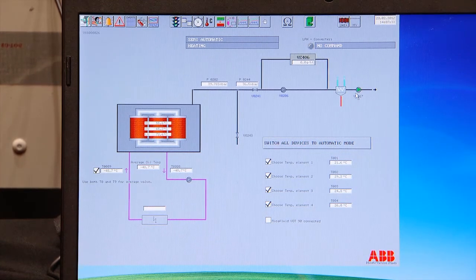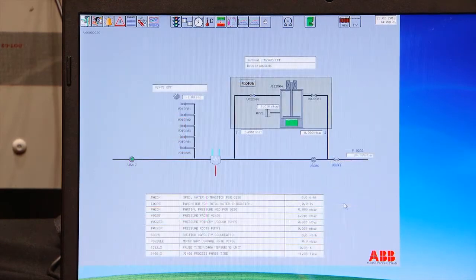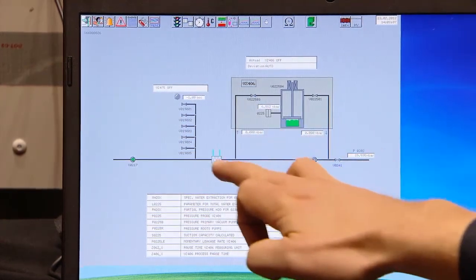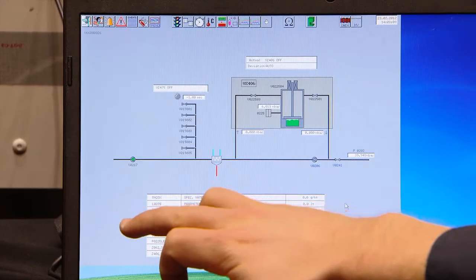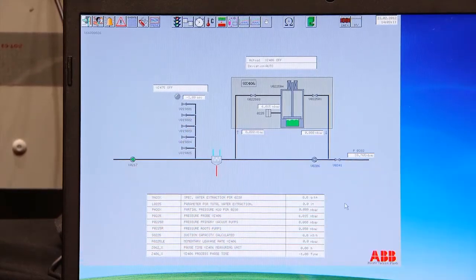Normally the booster is running as well, but now we have a special connection on this setup. The VZ475 is connected between the booster and the vacuum pump, and the VZ406 is connected over the roots pump. In your case you only have one connection point. If you connect them directly on the same T, you will have a bad reading here because the air inlet here will go directly to here.